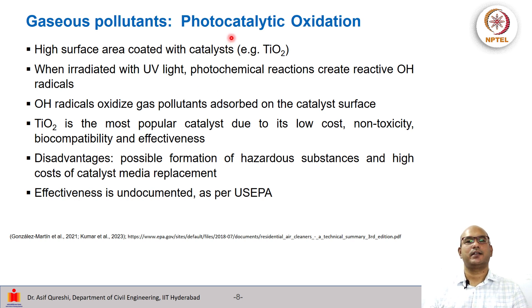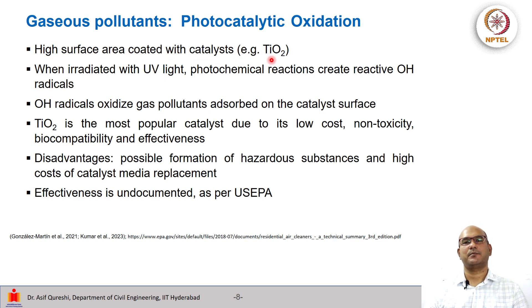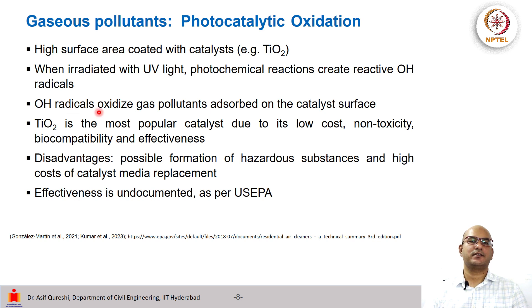Then we have photocatalytic oxidation, where the apparatus has a high surface area coated with a catalyst — for example TiO2 — so that when this catalyst-coated area is irradiated with UV light, photochemical reactions occur, resulting in the creation of reactive hydroxyl (OH) radicals. These OH radicals will then oxidize the gaseous pollutants that are adsorbed on the catalyst surface.